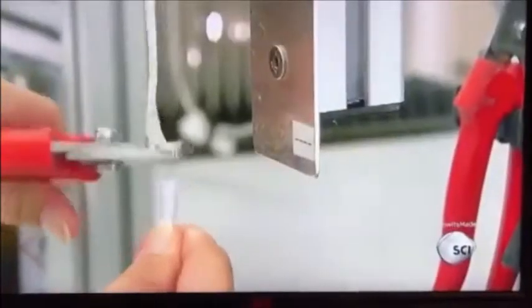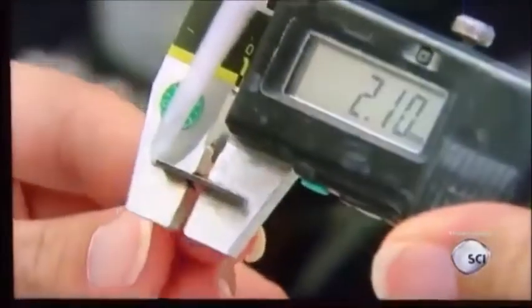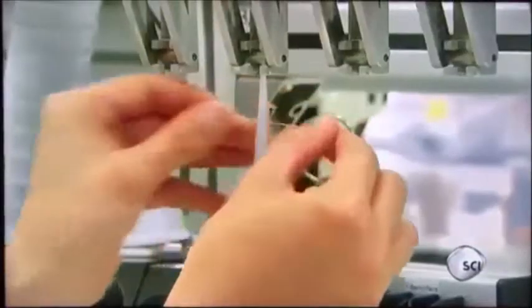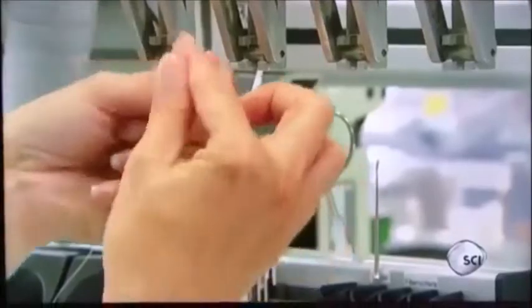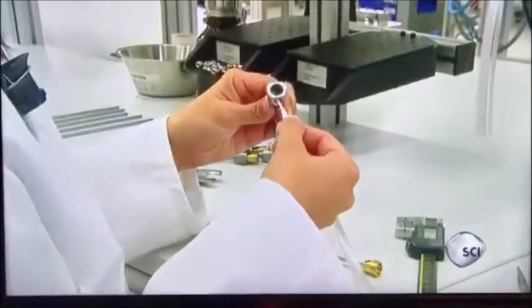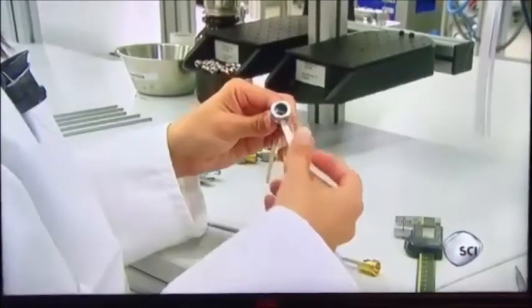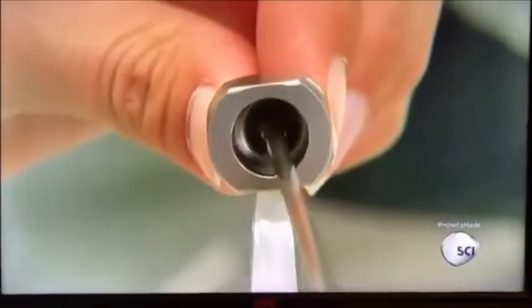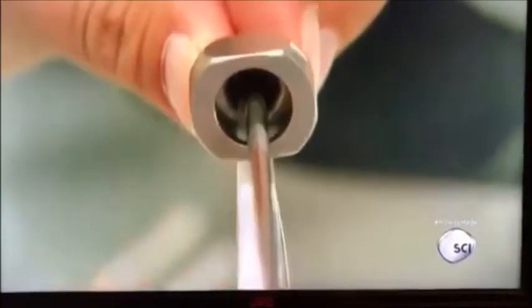Workers cut the bundle of optical fibers to the length required for the endoscope model they're making. Endoscopes vary in length and diameter, depending on the part of the body they're designed for. After verifying that the diameter of the bundle is correct, they tie the optical fibers with string to hold them together during insertion. Then, workers insert the fiber bundle between the inner and outer stainless steel sheaths that make up the main body of the endoscope, pushing the fibers down the length of the inner sheath.